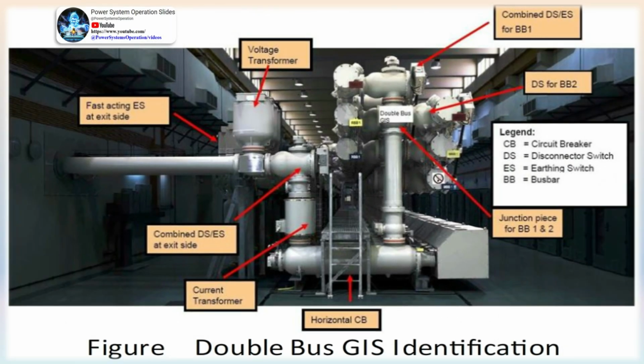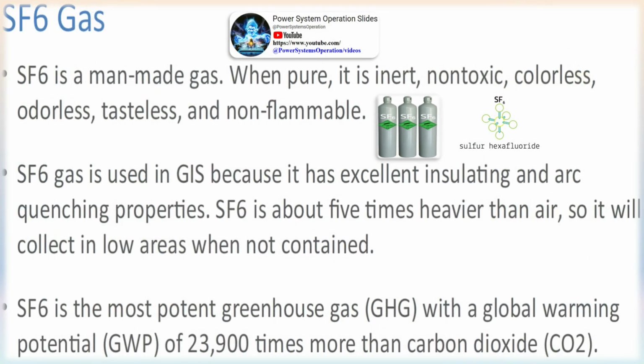Gas monitoring system. This includes an integrated alarm system, as well as automated tripping and lockout features in case of low-pressure conditions due to leakage. This is critical, as when the pressure of the dielectric gases drops, so does the insulating capability of the SF6 gas. High-voltage installations. Gas-insulated technology becomes more desirable as the voltage requirements increase.